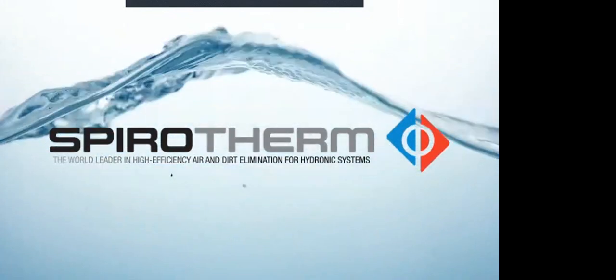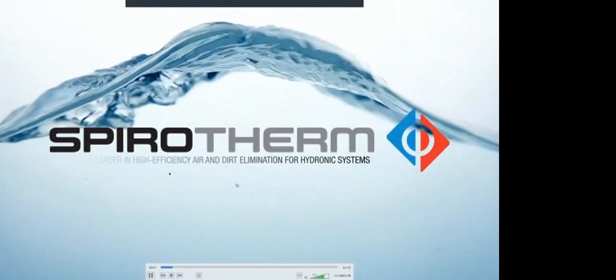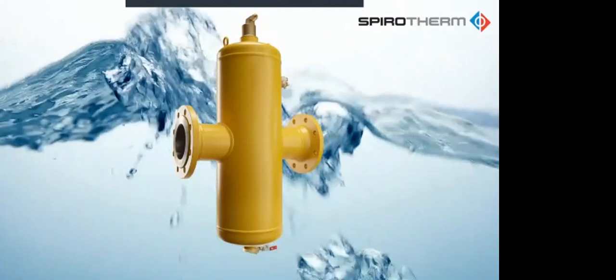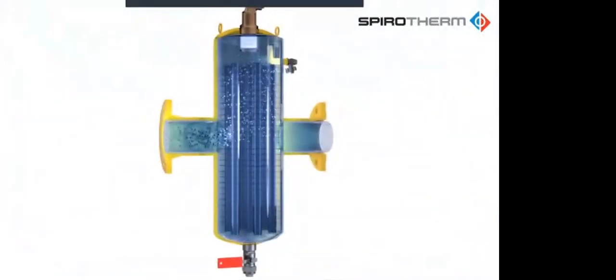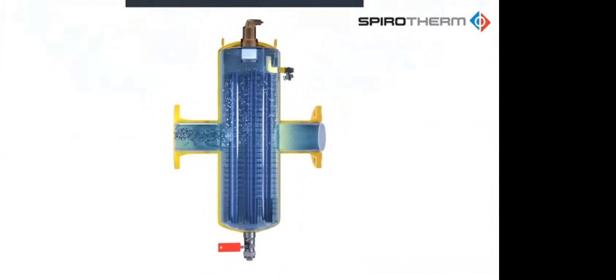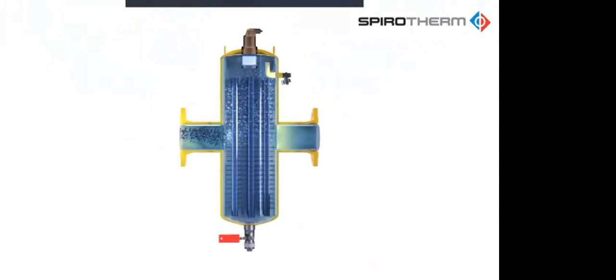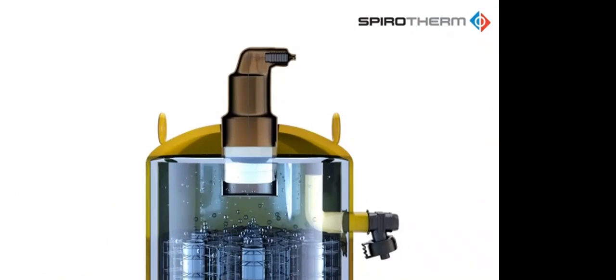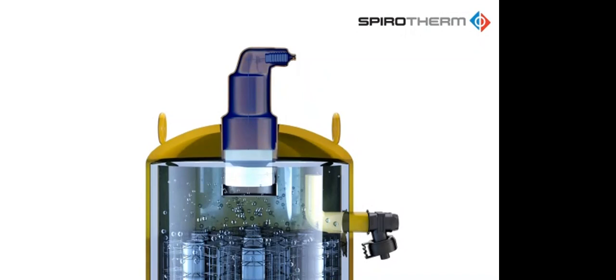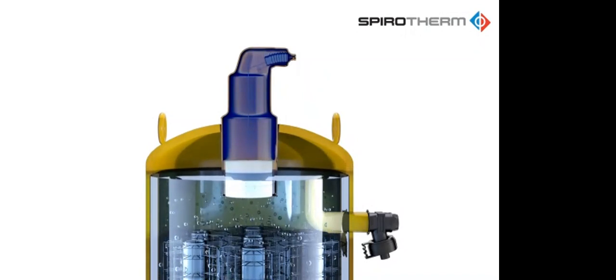The unique construction of the Spirotherm air and dirt combination separator allows for the removal of both entrained air and dirt particles. The patented Spirotube, the core of the unit, not only removes entrained air, but also countless microbubbles. Air in the system water can cause corrosion, reduced efficiency, poorly heated or inadequately cooled rooms, accelerated component wear, and ongoing complaints. The air bubbles rise and collect in the air chamber before they are vented from the system via an integral automatic valve.